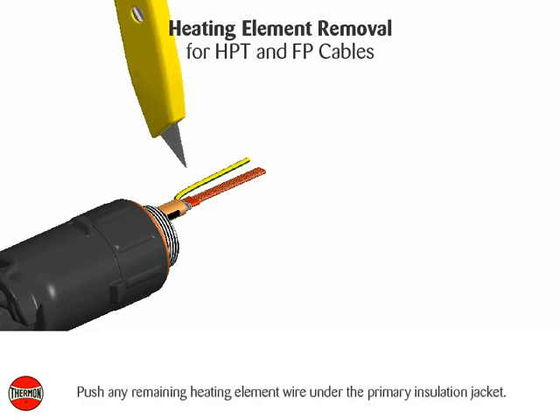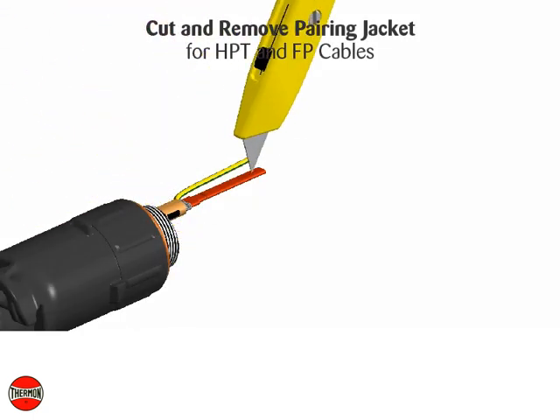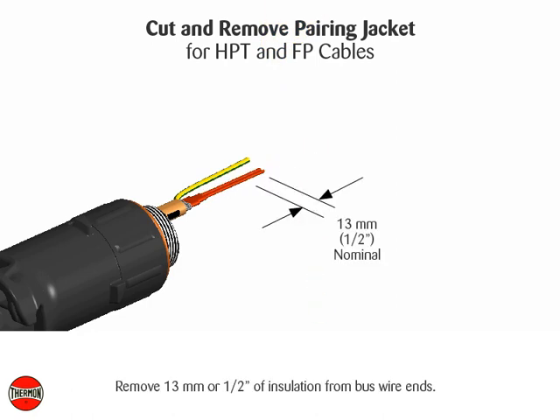Push any remaining heating element wire under the primary insulation jacket. Cut and remove pairing jacket. Remove 13 millimeters (½ inch) of insulation from bus wire ends.